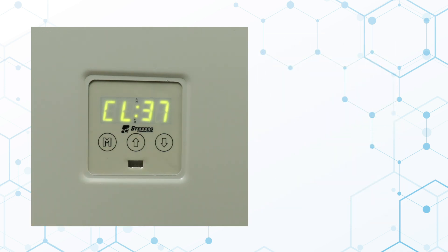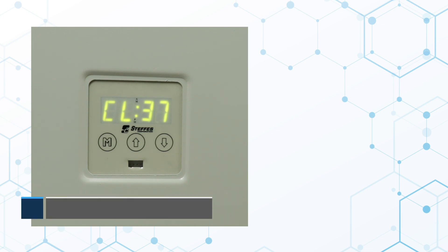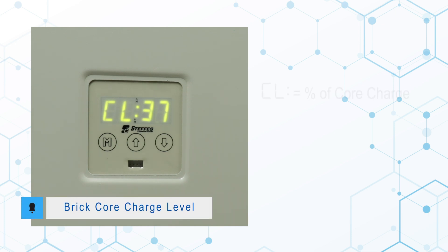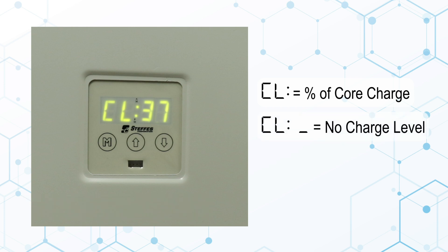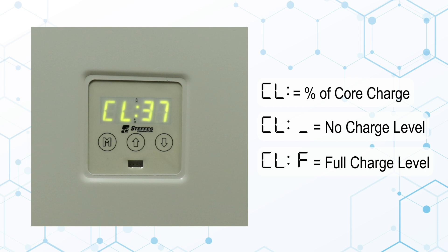Press the up arrow again. The display will show CL and a number, indicating the current percentage of heat stored in the brick core. CL underscore represents a charge level lower than the minimum core temperature, and CLF represents a full core charge level.